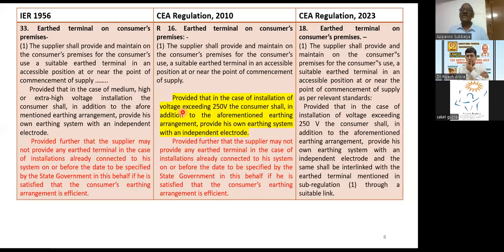So what is coming to this regulation 2023, what it says? It is 2023, just two regulations, same thing, but instead of 16, it is 18, because the regulation numbers will be jumping for some other regulations and other things. So here you can see what is the difference. The same thing. Here they have specifically pointed out that with an independent earth electrode, the same shall be interlinked with the earth terminal mentioned in sub-regulation 1 through a suitable link. So the consumer has to connect his earth conductor, that is the protective earthing conductor, to the supplier's earth neutral terminal, through a suitable length for testing purpose.